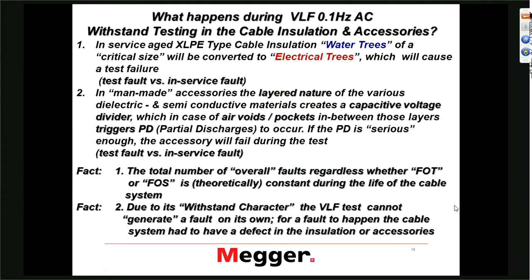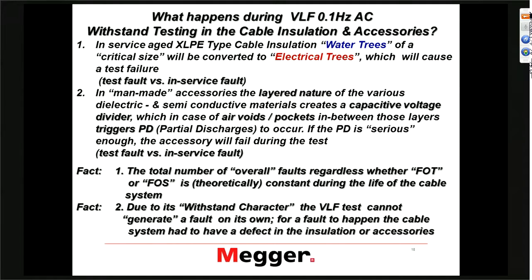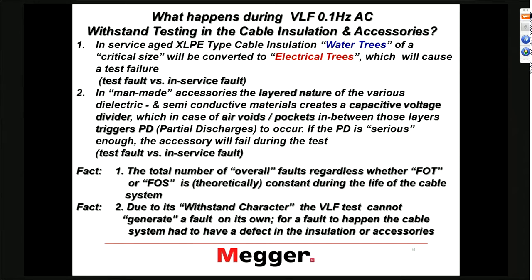It's always good to understand what happens during the VLF hypot test. When we changed from DC testing to VLF testing, the effects of 0.1 Hz AC are very different during the test on the cable installation than that of DC. In service-age cables, we have water trees, and once they reach a critical size, they will be converted to electrical trees and they will fail.